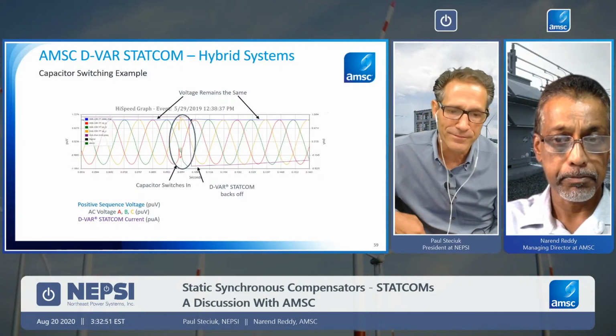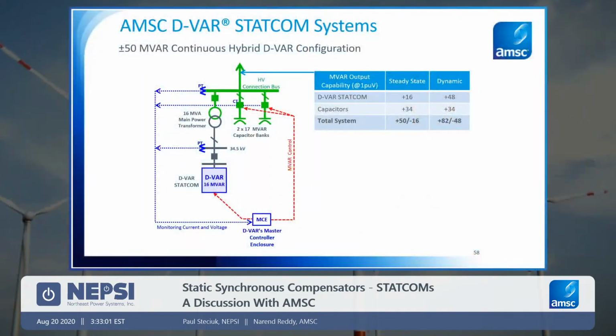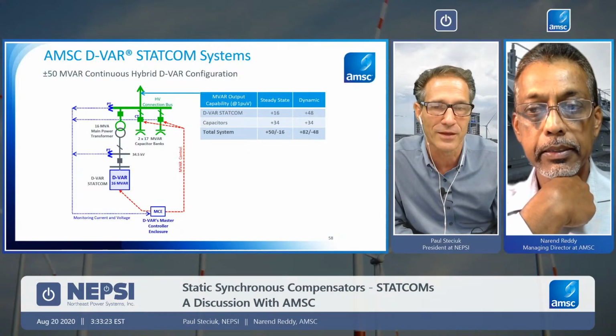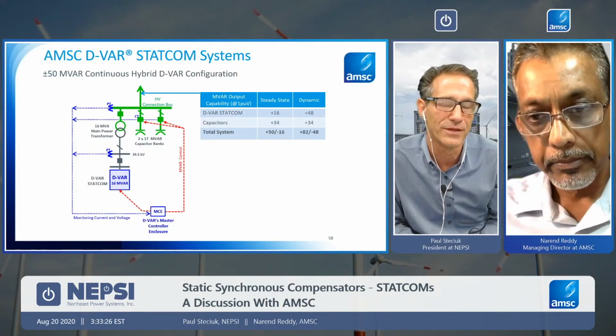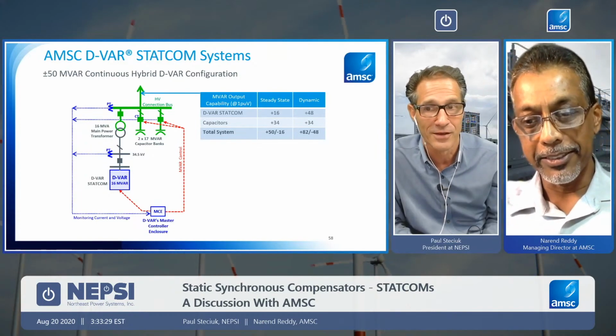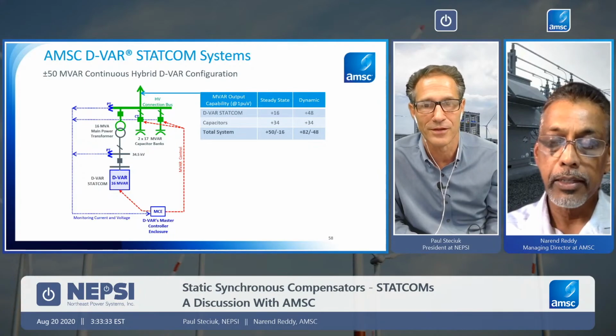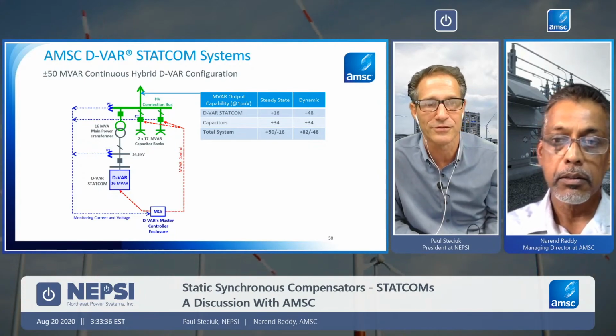Yeah, so maybe this is very interesting. Maybe you can go back to the previous slide, slide 58, and it's interesting. So what you're saying here is that we can have plus 82 megavars dynamic and minus 48 megavars inductive. So 82 megavars capacitive, 48 megavars inductive, basically for the price of a two-stage 17 megavar capacitor bank and 16 megavars of STATCOMs, the dvar systems, the STATCOM systems. So that's an amazing cost savings and a significant amount of megavars that you can dynamically switch.